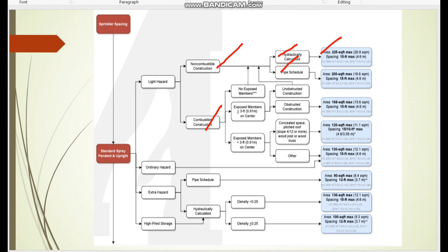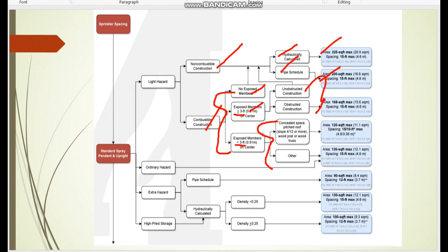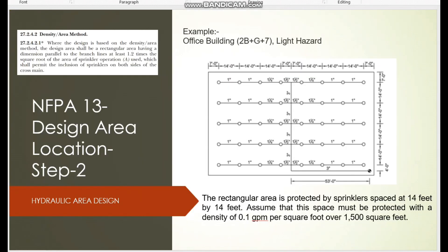From this decision tree, if the material is non-combustible, it directly leads to hydraulic and pipe schedule selection, where we can decide sprinkler spacing and the protection area. If it is combustible, we must examine three sub-categories: whether it is exposed or not, and if exposed, whether the distance is more or less than three feet, and whether it is obstructed or unobstructed. Based on the slope and those categories, we finalize the maximum spacing and sprinkler protection area.